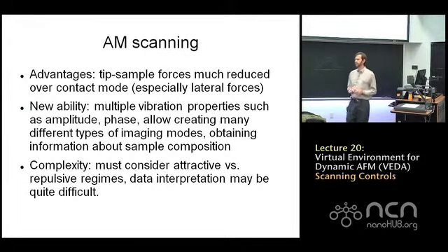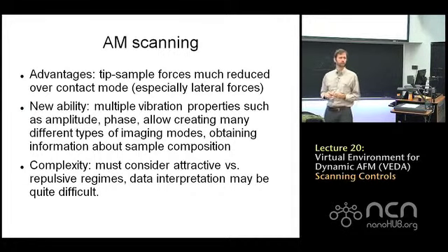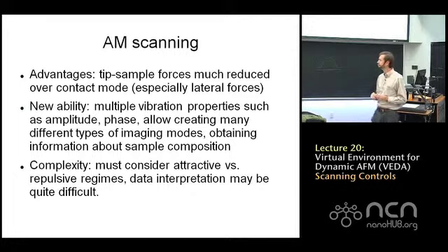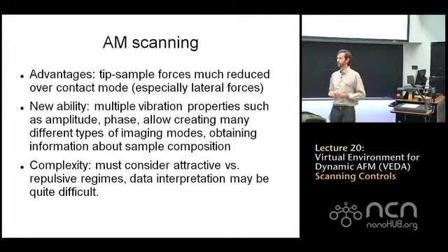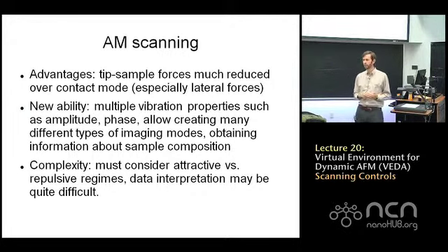As you guys have probably talked about in class, amplitude modulated scanning has a big advantage over contact mode scanning in that the forces are much lower, especially the lateral forces. That's why it's so popular in biology.